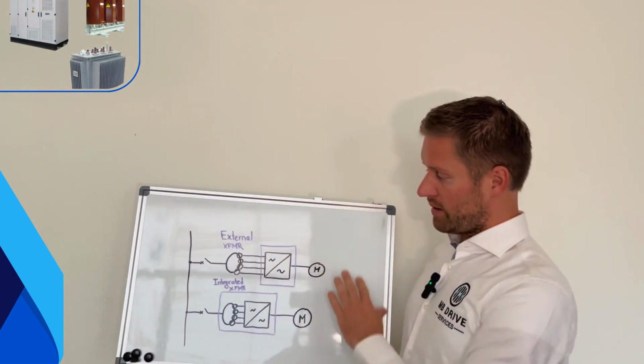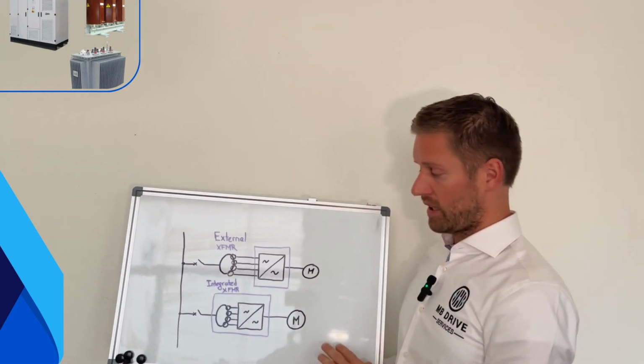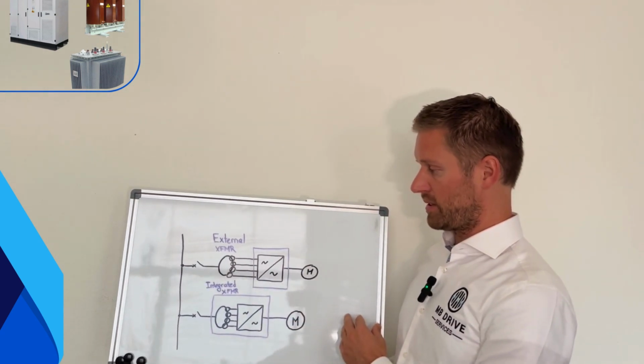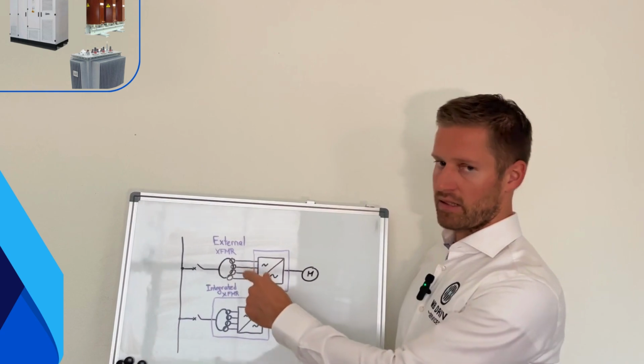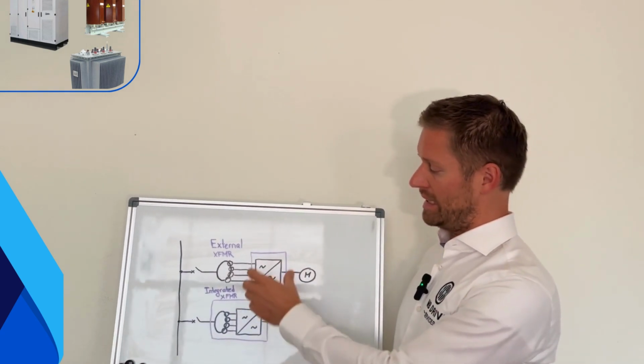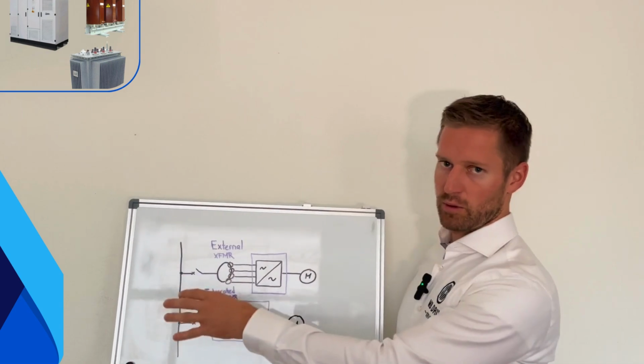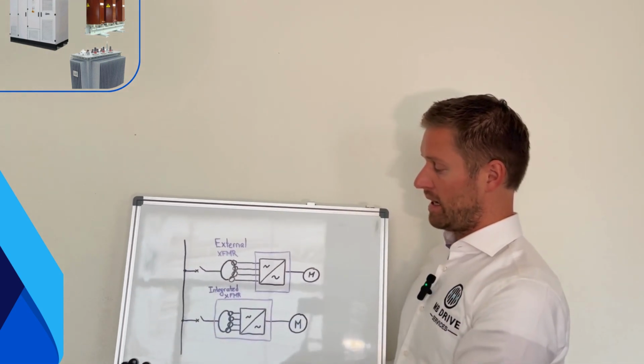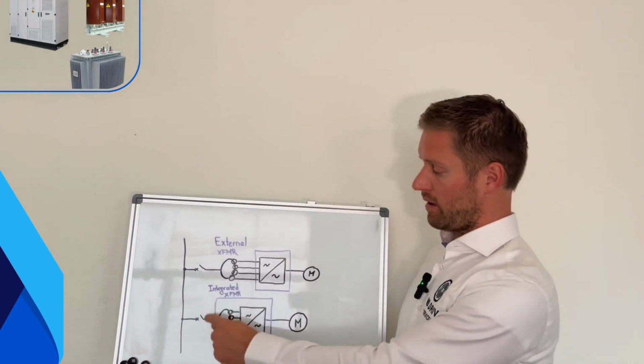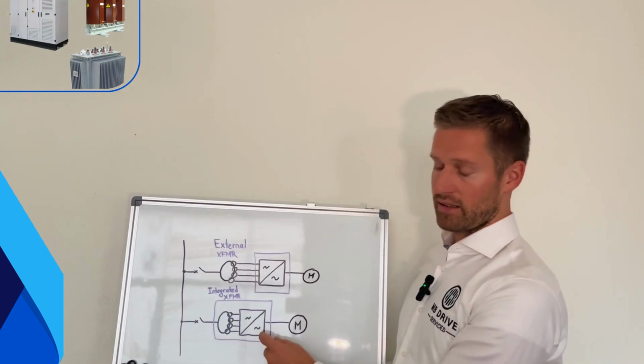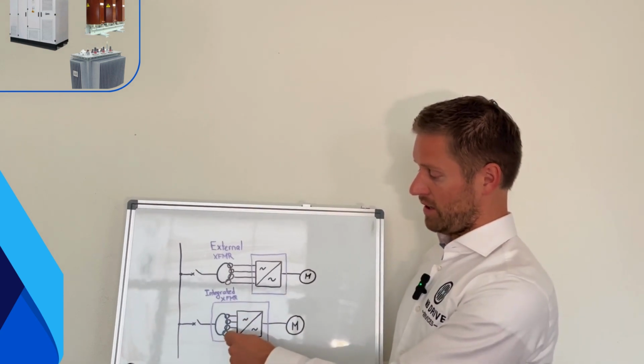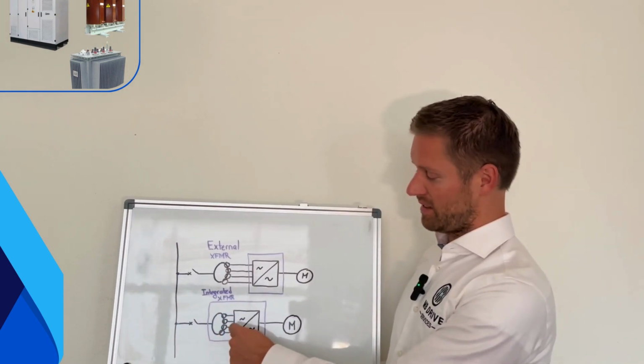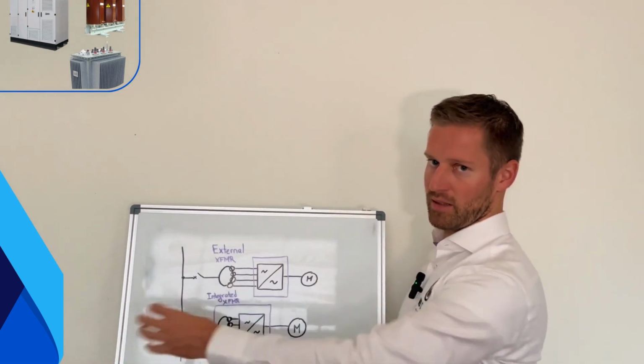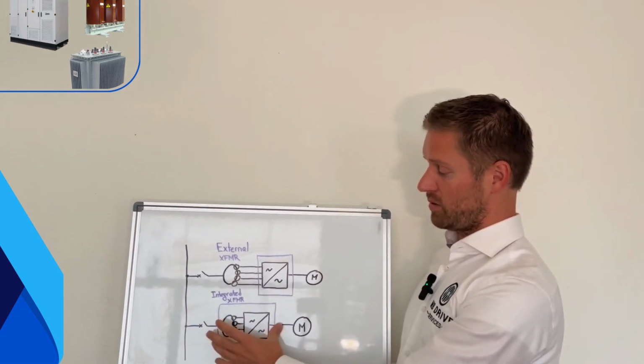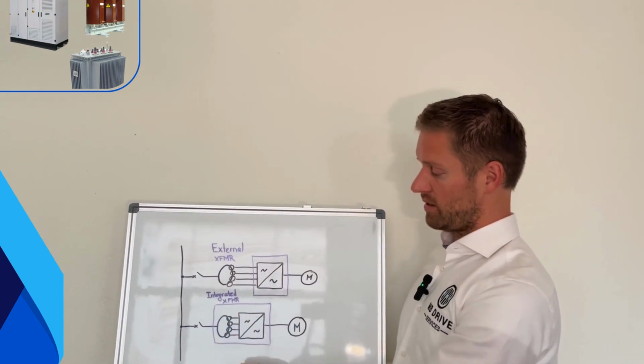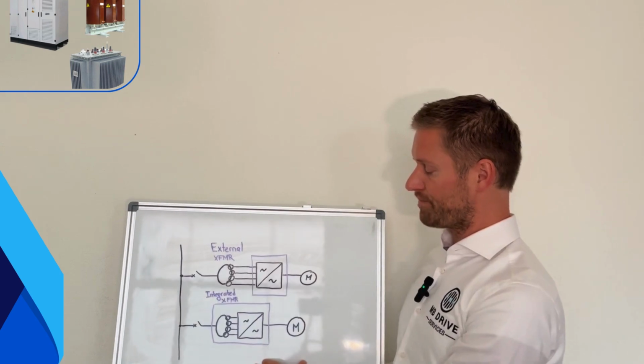Now if we look at the landscape of the medium voltage drives, some products or topologies are only available with the external transformer, so you just get separately the VFD and the transformer is a separate component. Other topologies are available with just the integrated transformer, especially those that have a lot of secondary windings. Then the cabling would be quite complex to have the transformer externally, so it makes sense to integrate it and to minimize the connections and let it be done by the manufacturer.